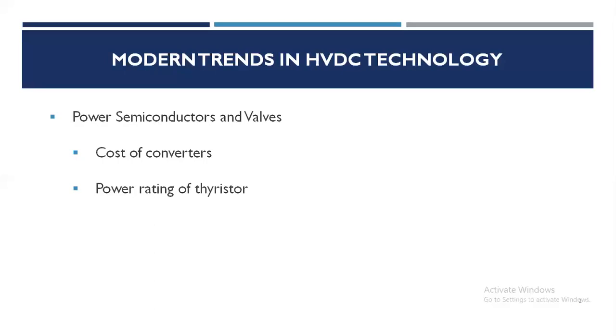As forced commutation converters operating at high voltages are uneconomic, the development of devices that can be turned off by application of a gate signal would be desirable. Gate turn off, that is GTO thyristors, are already available at 6 kV and 4000 ampere. However, the main disadvantage of GTOs is the large gate current needed to turn them off, and low switching speeds, which do not allow pulse width modulation.